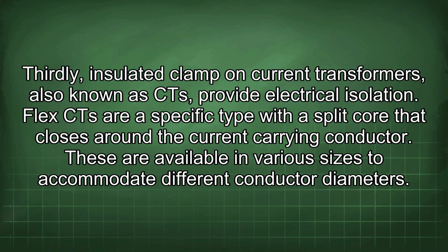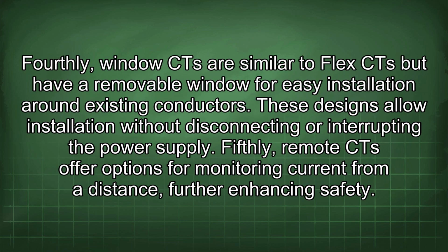Thirdly, insulated clamp-on current transformers, also known as CT, provide electrical isolation. Flex CT are a specific type with a split core that closes around the current-carrying conductor. These are available in various sizes to accommodate different conductor diameters. Fourthly, window CT are similar to flex CT but have a removable window for easy installation around existing conductors. These designs allow installation without disconnecting or interrupting the power supply.